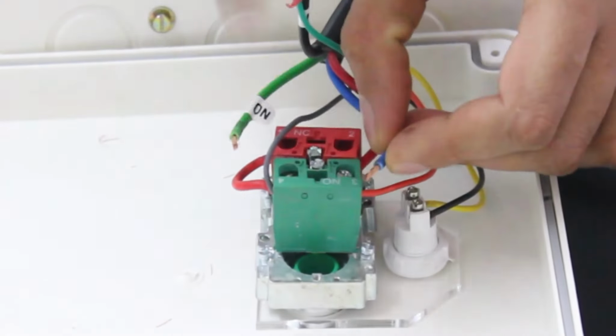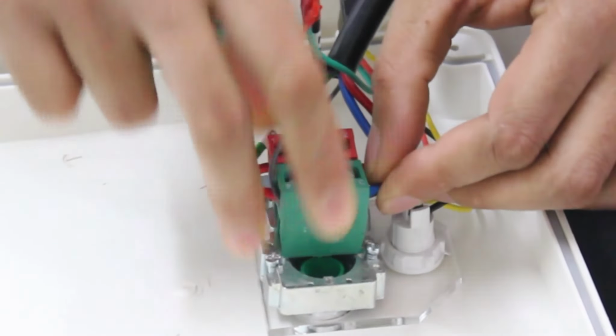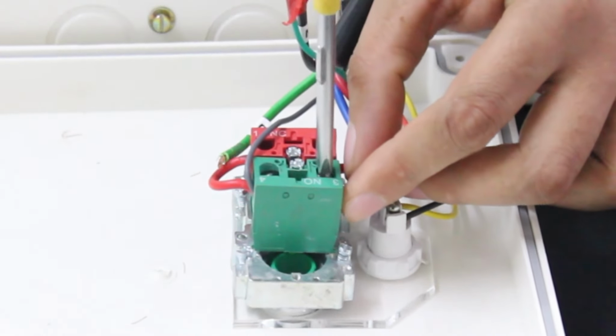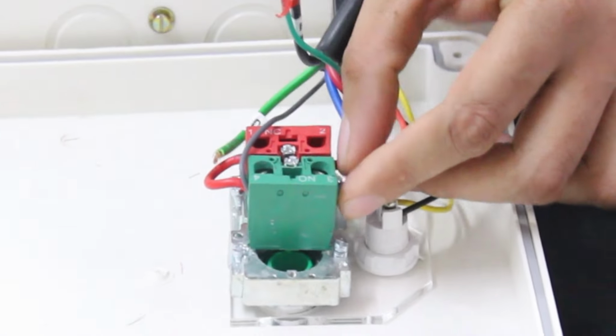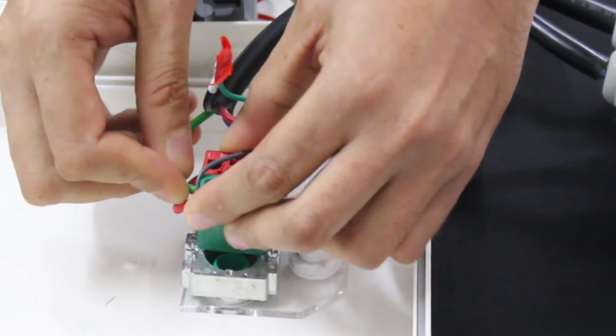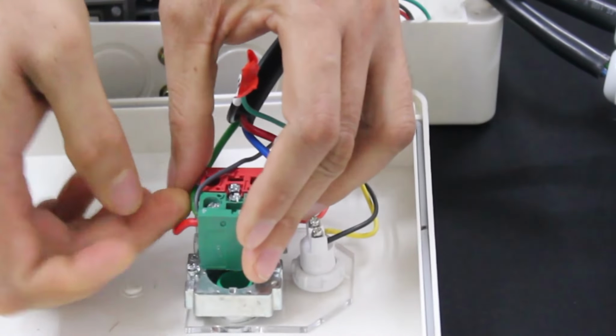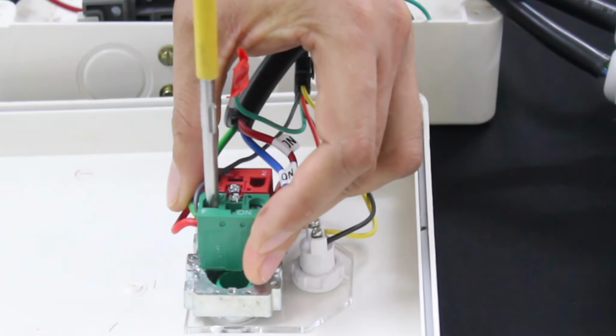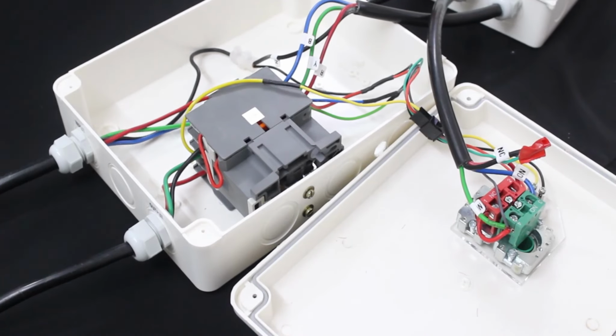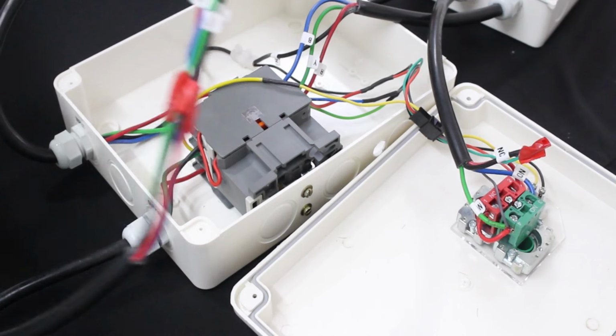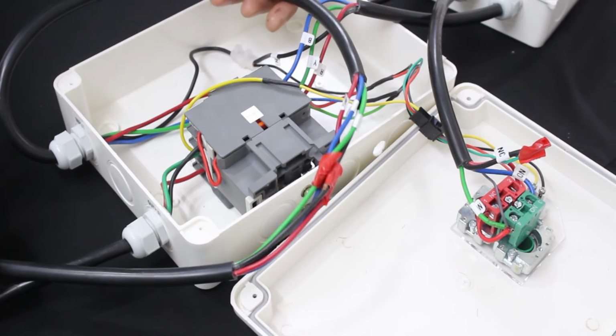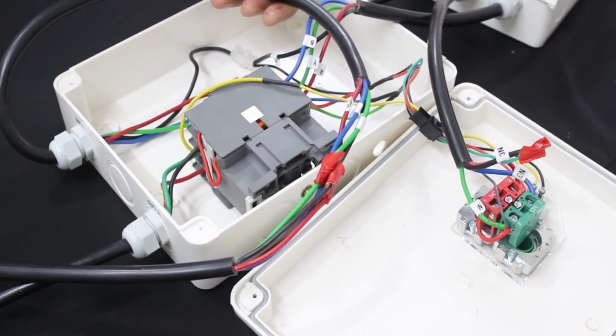Take the blue NO wire from the power module and connect it to the slot 3 on the NO terminal of the motor panel. Take the green NO wire and connect it to the last slot 4 on the NO terminal. Now run the wires of the MCB panel through the CTs, current transformers, from the power module.